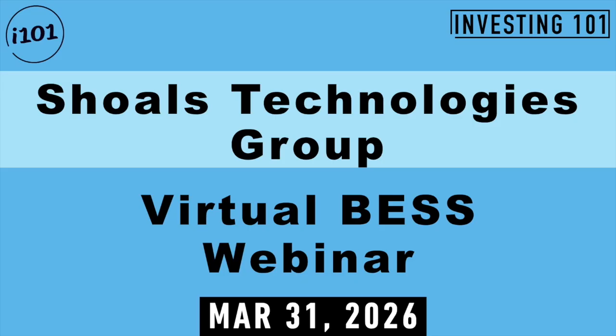It goes back to the prior question, which is what's the primary purpose of the energy that's being provided? In the upper right-hand portion of this slide, you see the substation, that's grid connected. It could also be natural gas turbines that are behind the meter that are connected. They then go to a transformer that steps down the voltage to the point where an inverter can take that power in. It then goes through, we're hoping in every case, a Shoals recombiner, which then goes to a battery stack, a battery container, and charges the batteries. The batteries then are used to discharge through an inverter that steps it down to a voltage the data center can use, and then it feeds into the data center as AC. So you think of that power flow coming from the grid or natural gas turbines.